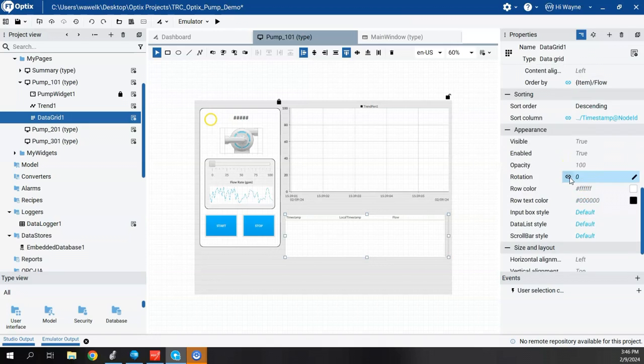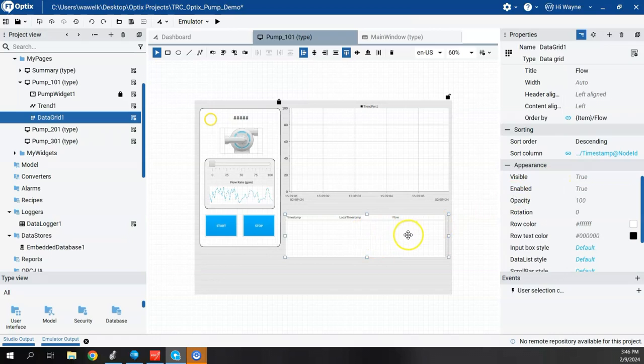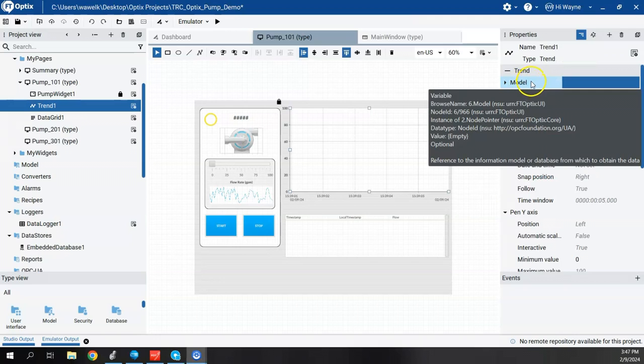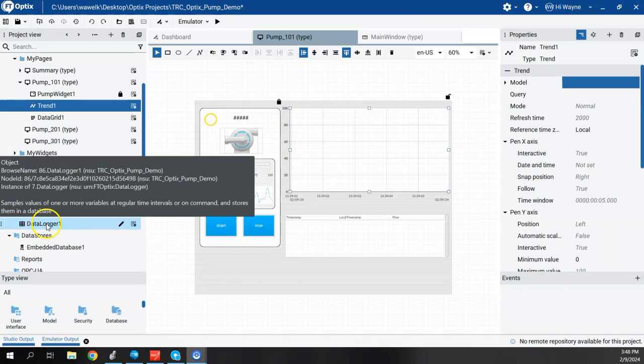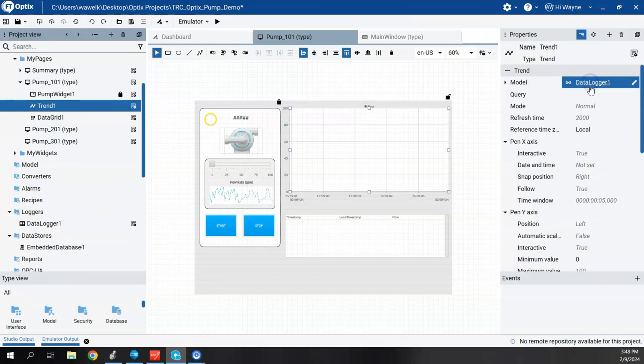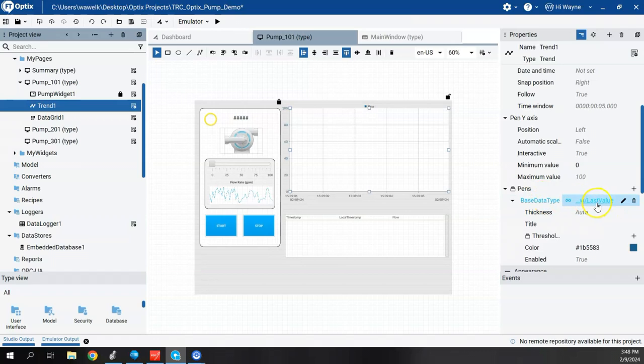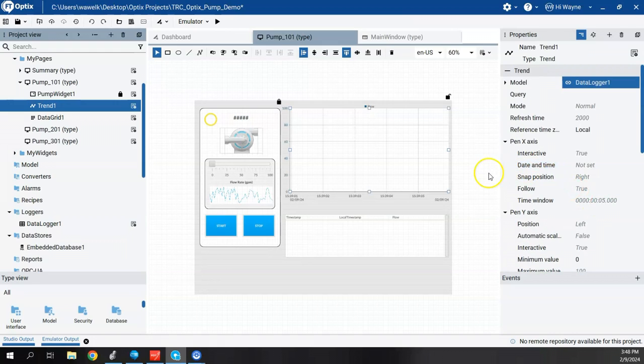You can scroll through other properties and set them to your liking. To tie the trend chart to historical data instead of real-time data, I click back on the trend and get its properties. Under Trend Properties there's a Model field — I drag the Data Logger 1 onto the Model. When that happens, the Flow last value under the Pen changes — it was previously tied directly to the controller tag, and now it's tied to the tag through the data logger.